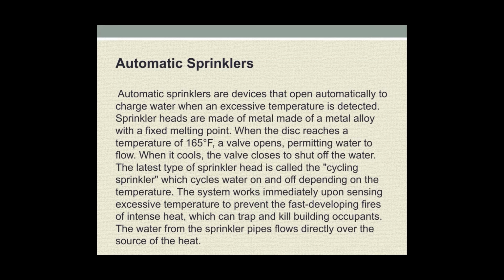Next, automatic sprinklers. Automatic sprinklers are devices that open automatically to discharge water when an excessive temperature is detected. Sprinkler heads are made of a metal alloy with a fixed melting point. When the disk reaches a temperature of 160 Fahrenheit, a valve opens permitting water to flow. When it cools, the valve closes to shut off the water. The latest type of sprinkler head is called the cycling sprinkler, which cycles water on and off depending on the temperature. The system works immediately upon sensing excessive temperature to prevent fast developing fires of intense heat, which can trap and kill building occupants. The water from the sprinkler pipes flows directly over the source of the heat.